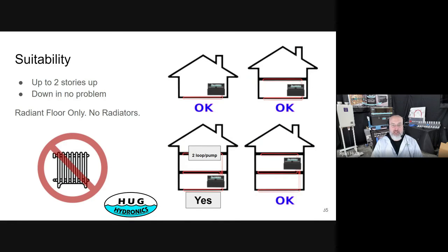Suitability: put it on the main floor, the same floor you're heating, that's great. You can go up and down too. You can even go up two stories. For a while, this was here because that wasn't a recommended option. Now we've tested it and proved it out. The pumps push plenty hard to fill those loops up high. I wouldn't go up three stories.